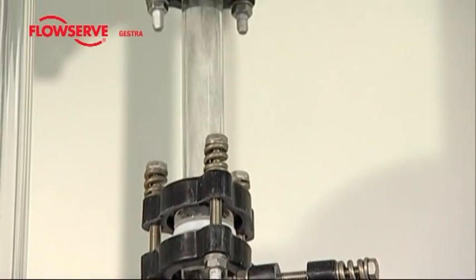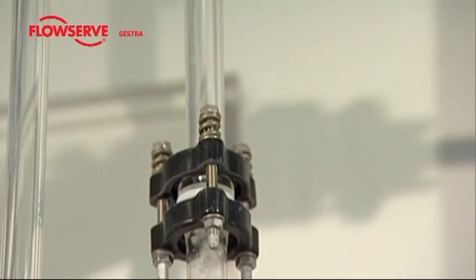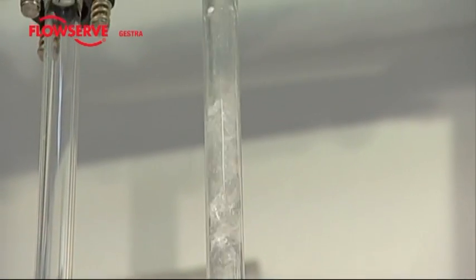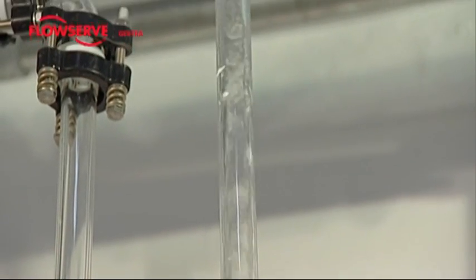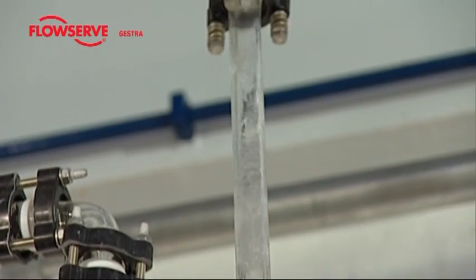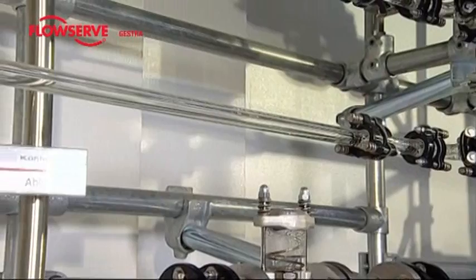The shutoff valve must be opened very slowly to ensure that the number of steam bubbles passing into the water is kept as low as possible. Once the entire body of water has warmed up to boiling point, the steam bubbles condense at only a very slow rate. There is then no longer any danger of Waterhammer. The experiment is repeated a second time.